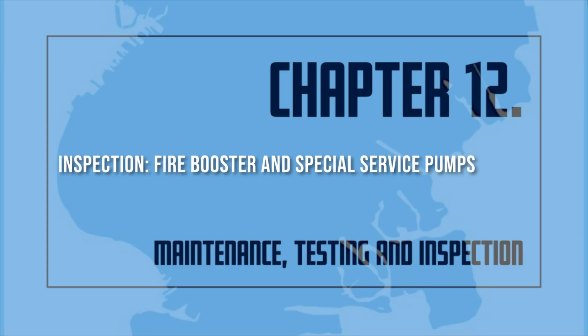Weekly visual inspections shall be made to ensure that the pump suction and discharge and the bypass valves are fully open, all piping is free of leaks, suction line pressure gauge readings are normal, and that the reservoir is full. System line pressure gauge readings are normal and that the wet pit suction screens are unobstructed and in place. Diesel engine fire pump system.